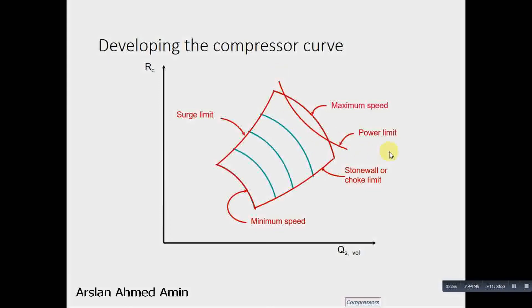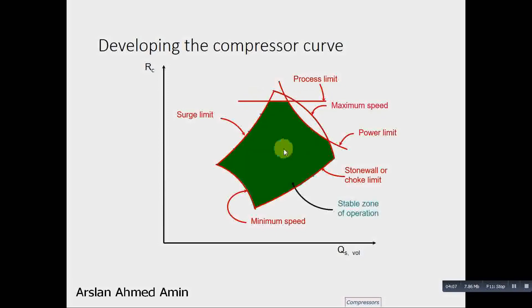And this is the process limit that this compression, this pressure ratio must not be exceeded. So this is the safe region where we want our compressor to continue. Our main purpose would be to run the compressor in this region. And to achieve this, we use the anti-surge control system.